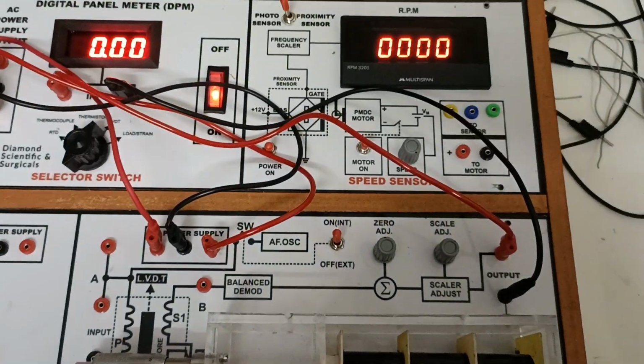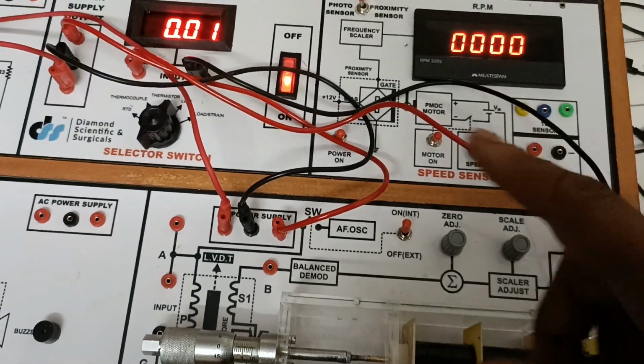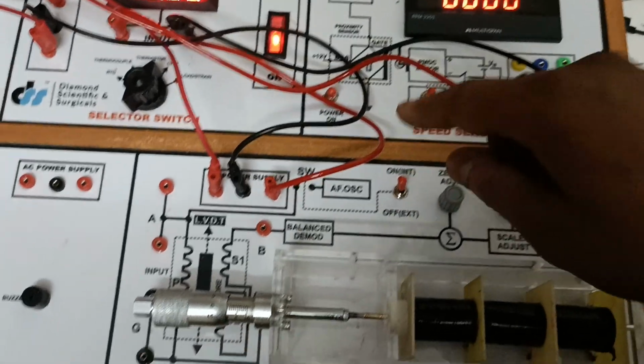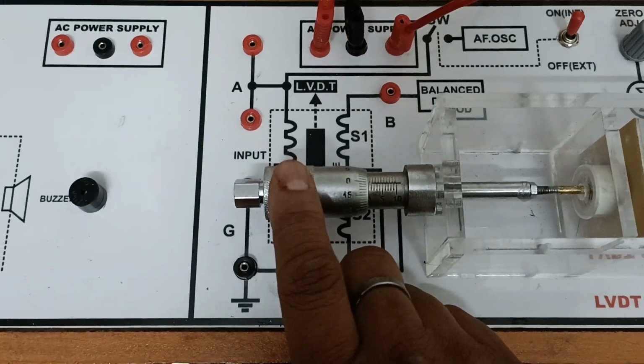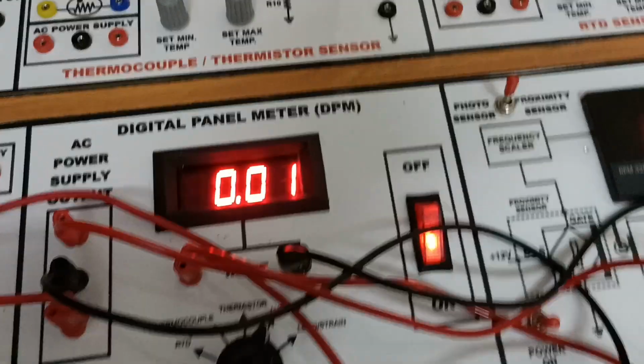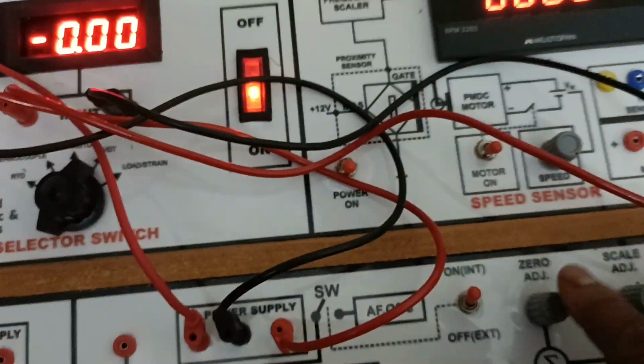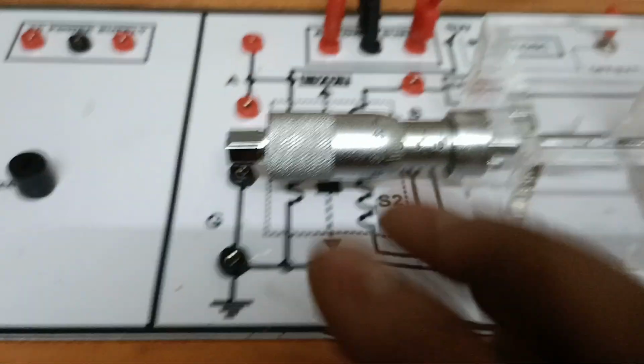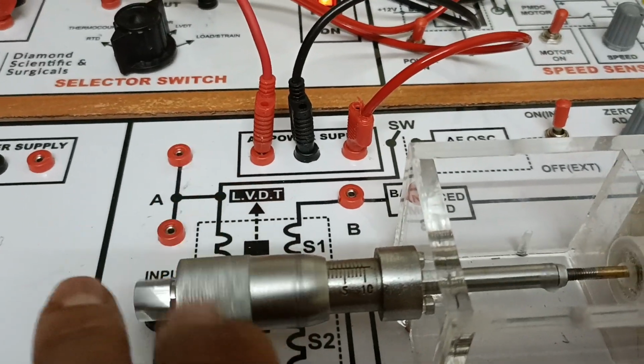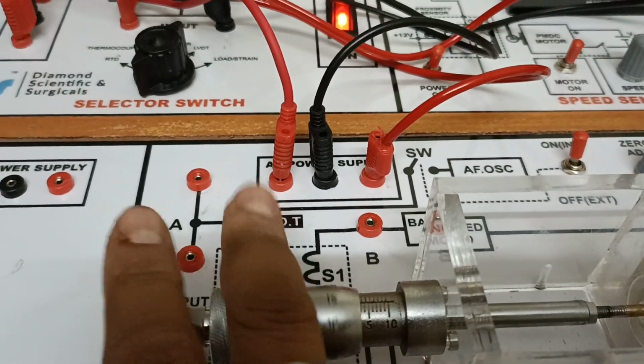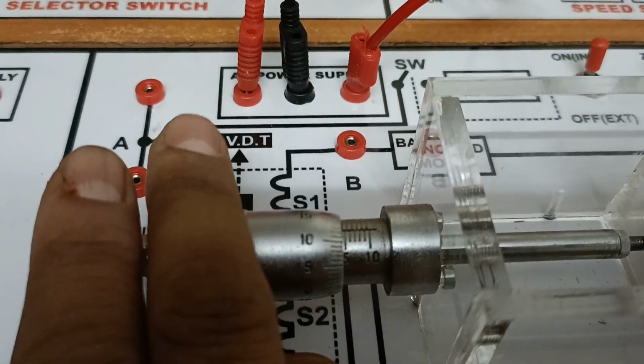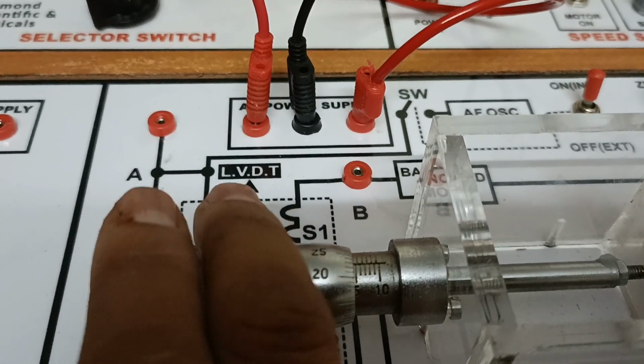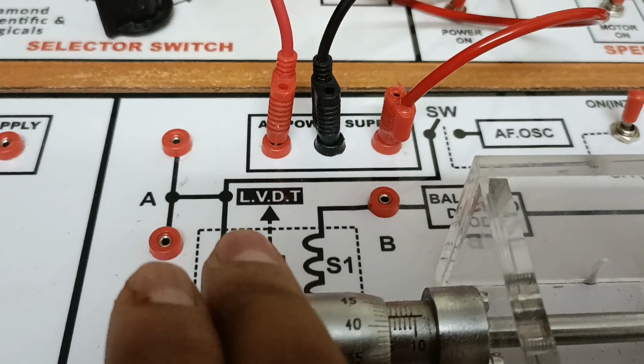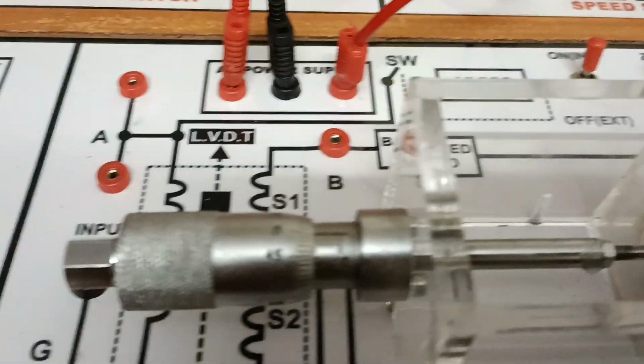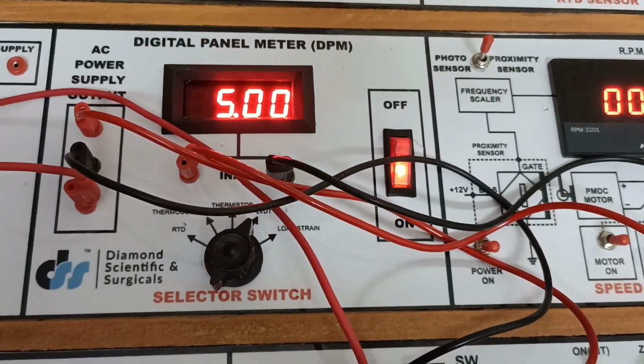In this experiment, connect the circuit according to this and put the switch to internal mode. First of all, set the micrometer position to 0 mm. If the meter does not show 0 displacement, set the 0 adjustment port. Now move the LVDT to the 5 mm displacement. Coincide the 0 to the 5 mm. Okay, like this. And the displacement will show on the digital panel meter.